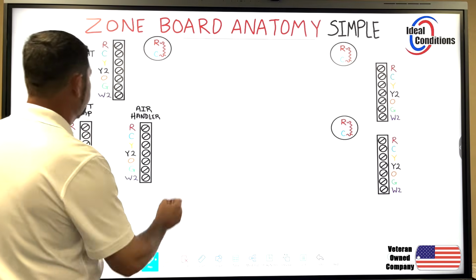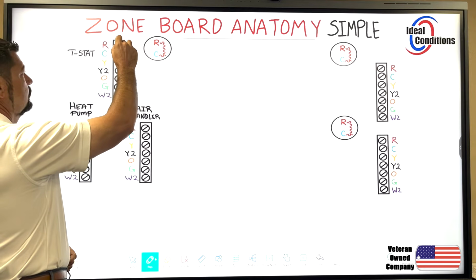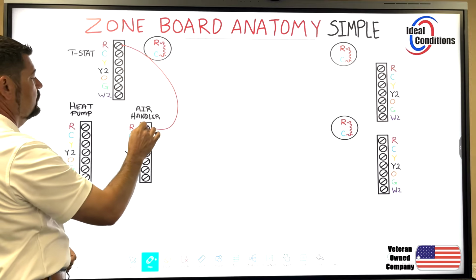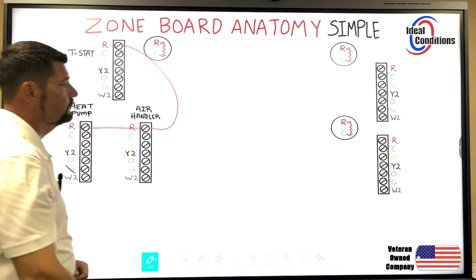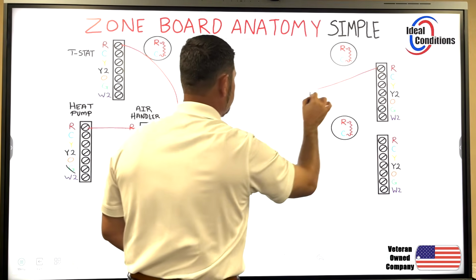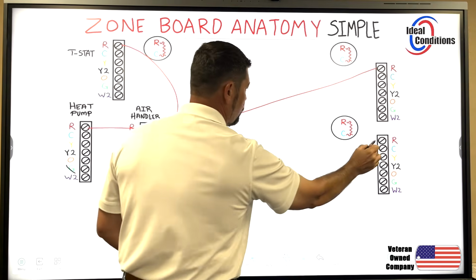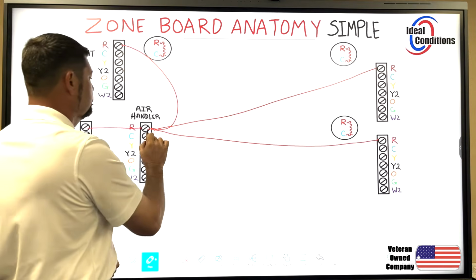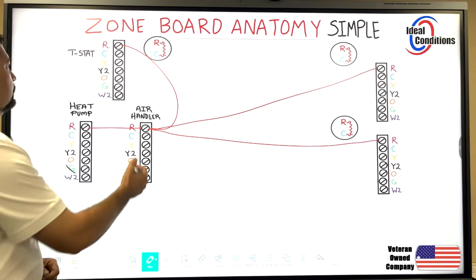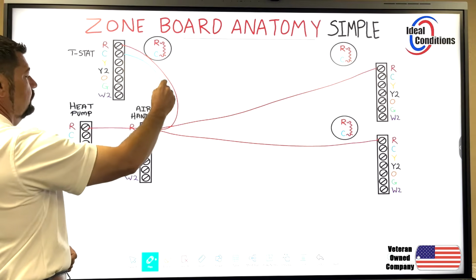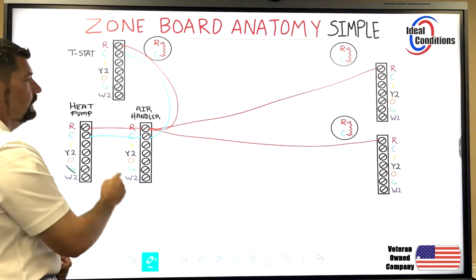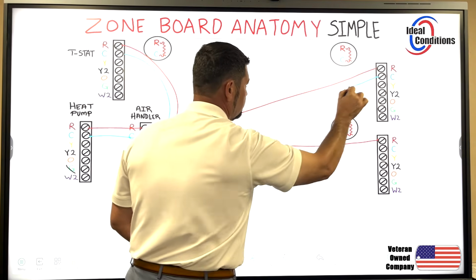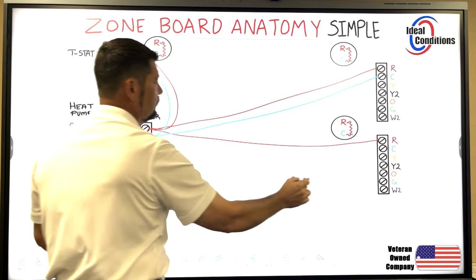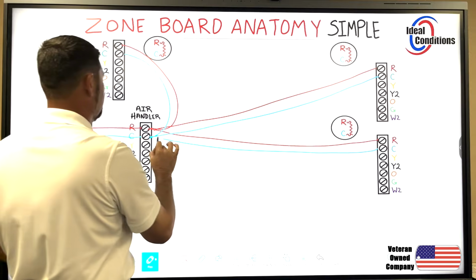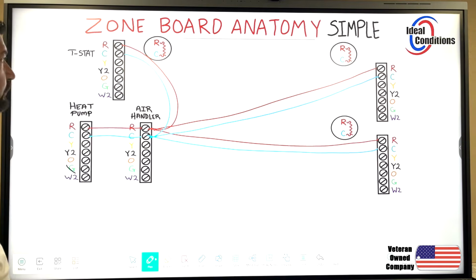We're going to start off with R to R, R. Let's go ahead and wire this thermostat over here too to the air handler. And let's go ahead and wire this thermostat over here to the air handler. We're going to take our commons back and bring that outside. We're going to take our common from this thermostat and our common from this thermostat. And so far nothing crazy's happened. We have a display on all 3 thermostats.